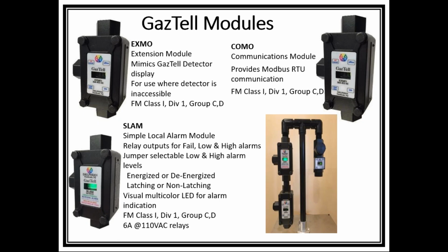It is also FM Class 1, Div 1, Group C and D, as all three modules are. The SLAM is the next module in the series that's probably of most importance because that's what you're going to use to actually trigger alarms. Although the detector head has a 4 to 20 output, in many cases you might want a horn, a light, a relay contact out in the field, maybe even to do an emergency solenoid shutdown where you shut down the electricity or you close a valve where the gas is leaking from.